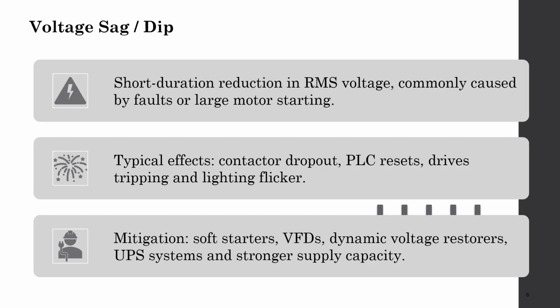Let's talk about voltage sag or dip. It is a short duration reduction in RMS voltage, commonly caused by faults or large motor starting or large load, and typically affects contactor dropout, PLC resets, drive tripping, and lighting flicker. For mitigation of this issue, we should use a soft starter or VFD for the large motor, also dynamic voltage restorers, UPS systems and stronger power supply capacity.